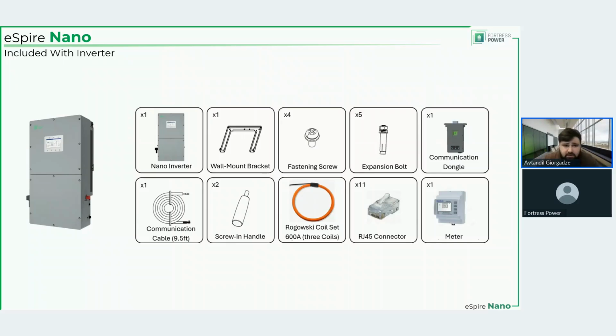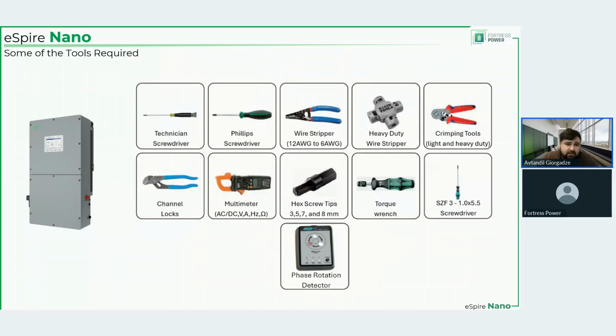With these inverters, it seems like we'll not have CTs as such at any point. So even if I mention CT somewhere during the presentation, assume that I'm referring to the Rogowski coil. CT is just something that we're all used to, and sometimes, perhaps mistakenly, we refer to Rogowski coils as CTs, but they work a little differently than CTs. RJ45 connector and the meter. Now we will talk about the meter and the Rogowski coil later, but quick thing: the meter will always be used, and although we have ports available for the Rogowski coil set or CTs directly to be connected to the inverter, the meter is a must, right?